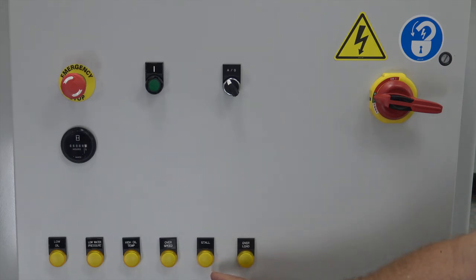Stall means that your pump is set in one position too long without a proximity switch. Once it's breached that time period in the program, it shuts down on stall. Again, push your emergency stop in and out and you can reset that and of course restart. Overload on a machine simply means that there's an overload relay inside your electrical panel, and it is showing a fault error. There's 6 different reasons that overload can shut down. So this is just telling you that it's showing a fault. To get the specific fault on that, they're labeled on the side of the overload itself.